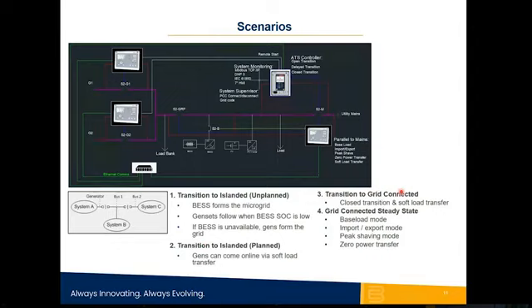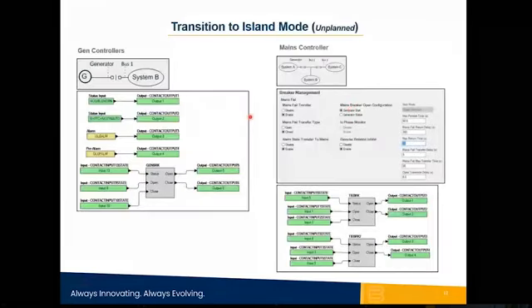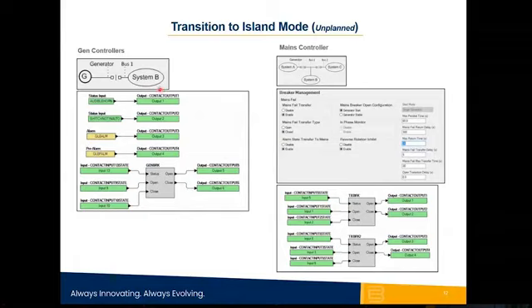And then in a grid connected steady state, we want to be able to control the gens in all these different modes. Zero power transfer you can think of as storm mode, where the system is parallel to the grid, but it's not importing or exporting. It's just ready to take over in the event that there's a utility failure. So here are some settings and logic that I'm showing would have to be implemented in the various types of controllers to achieve each of these different modes. In your gen controllers, your system breaker configuration would be generated to segmented system. And here's some basic logic that can help achieve that.